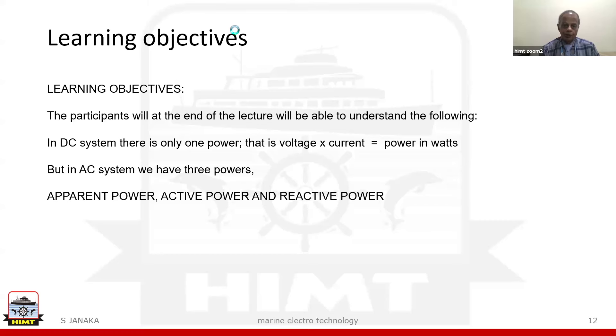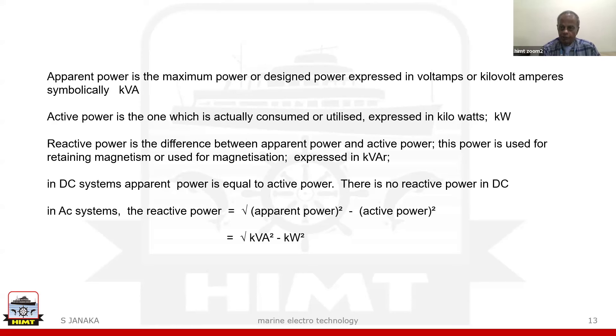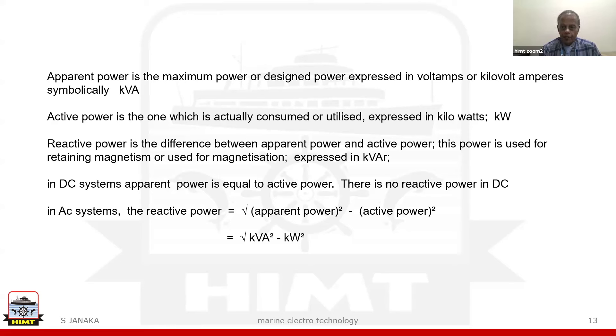The balance is called reactive power. This apparent power is the maximum or designed power, expressed in kVA. Active power is in kilowatts. Reactive power is the difference between apparent power and active power, represented as kVAR. Reactive power equals the square root of apparent power squared minus active power squared — kVA squared minus kilowatt squared.